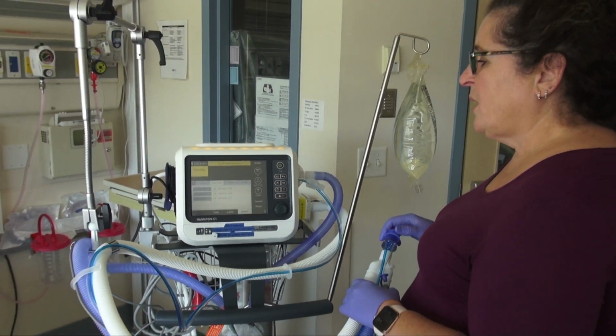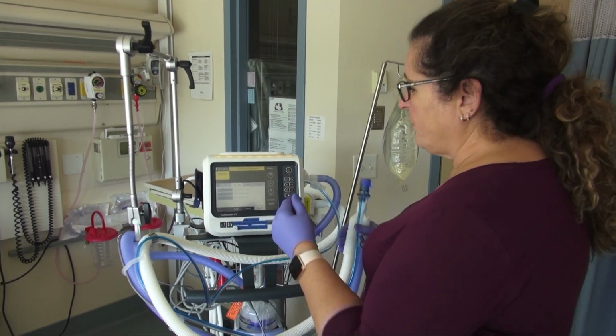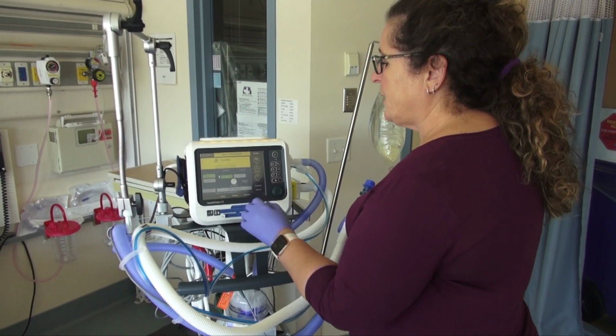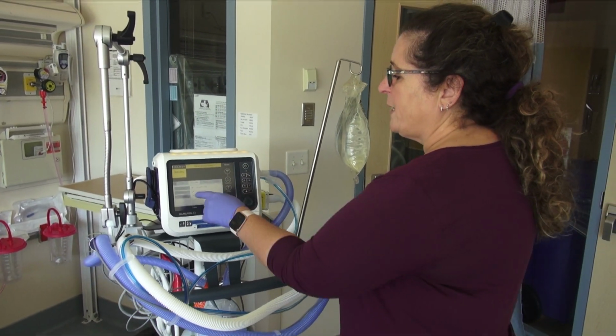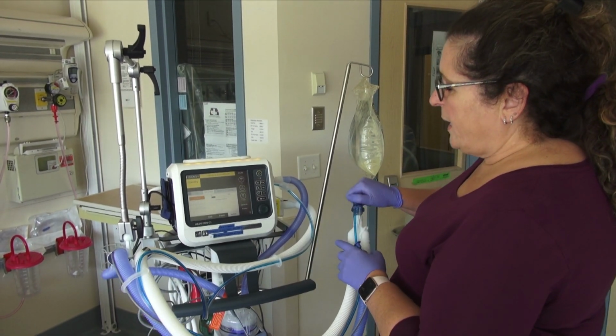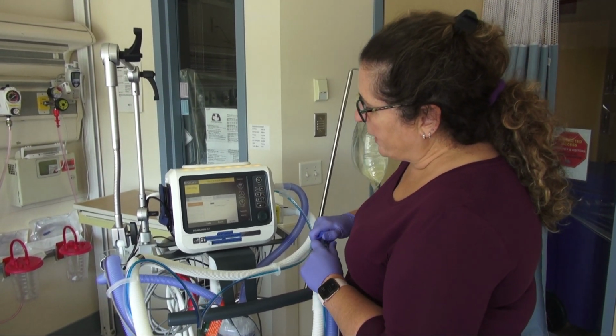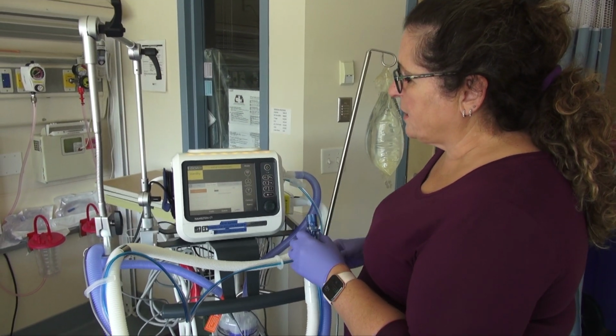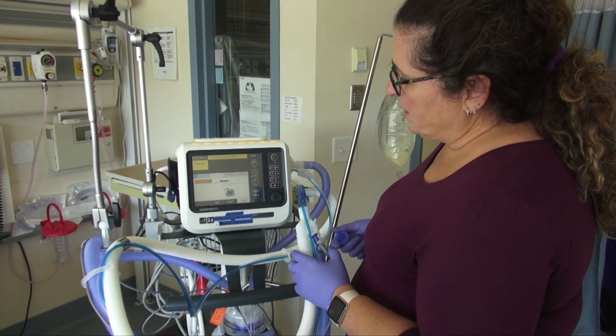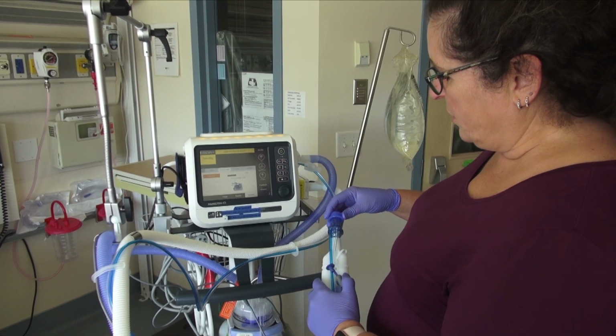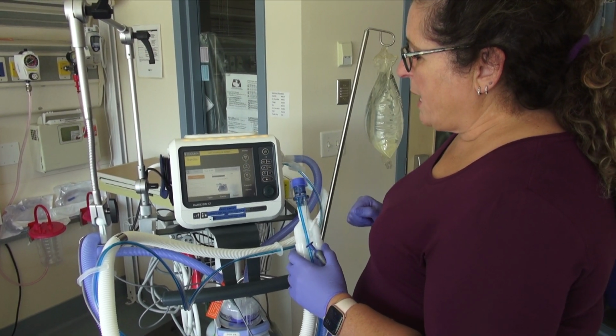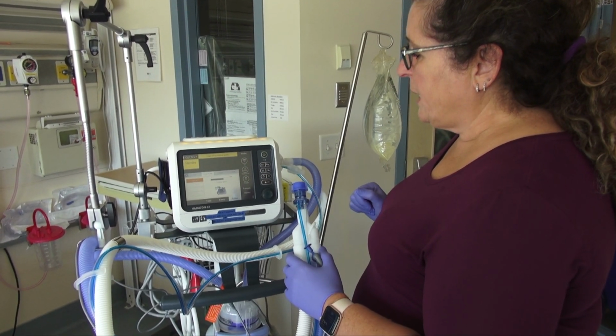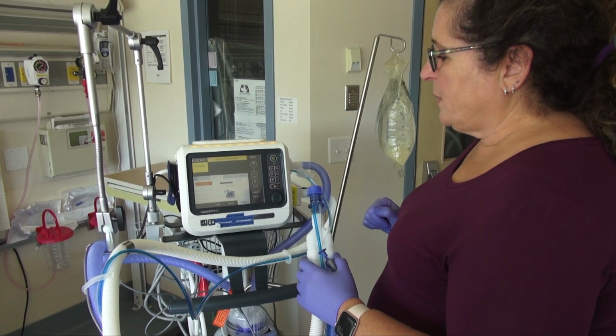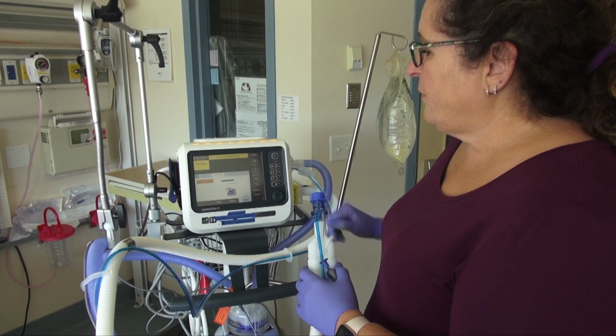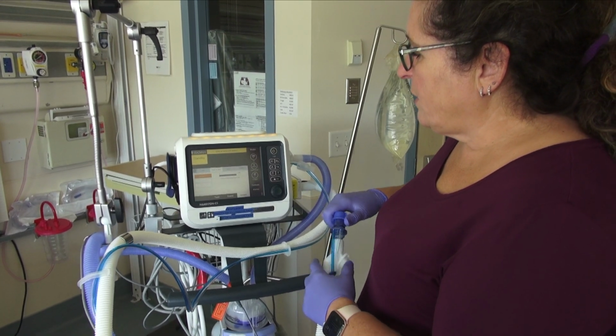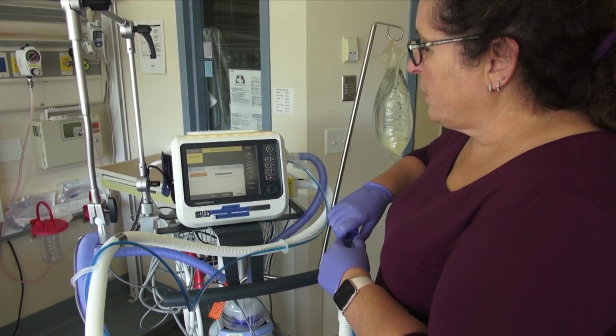the patient. So, going forward, have your gloves on, press your leak test. If you time out, if you wait too long, press your leak test again, and it will give you instructions right on the screen. So this is saying disconnect the patient. We have the patient disconnected. Now it's saying block the circuit. I just put the blue cap back on so we can keep it clean. It will run through its testing. And if you watch the screen, it will give you everything that it needs to. Reconnect the breathing circuit.